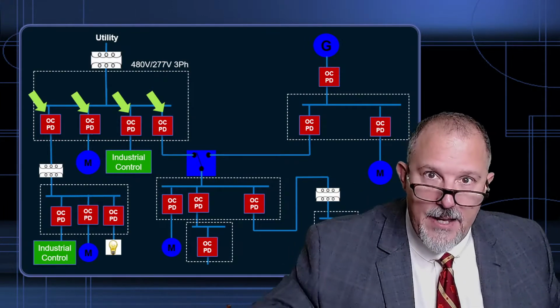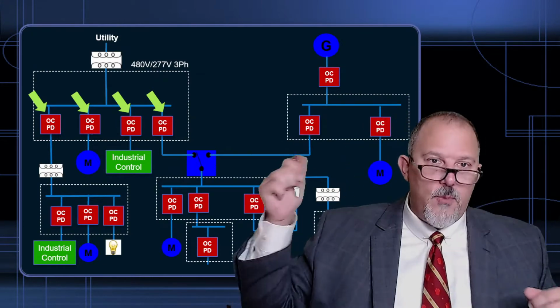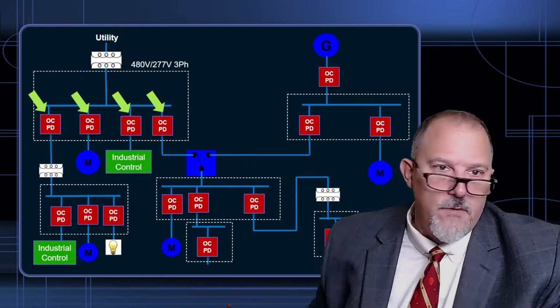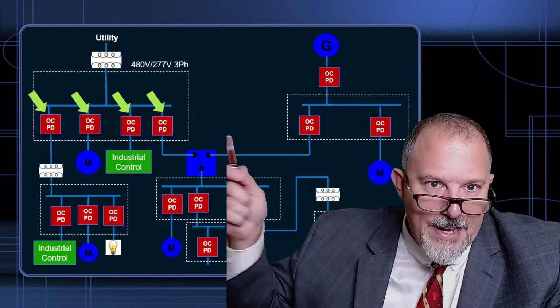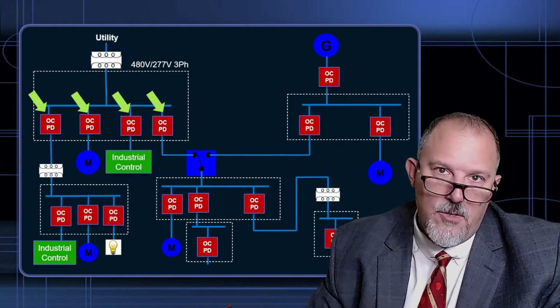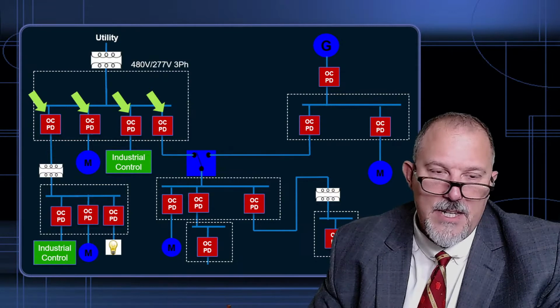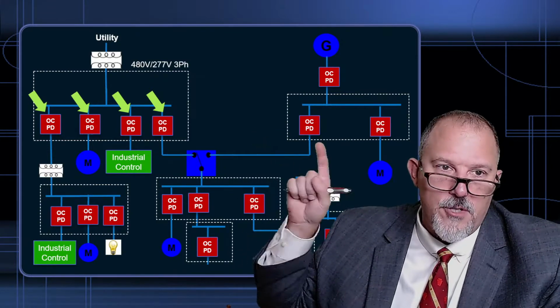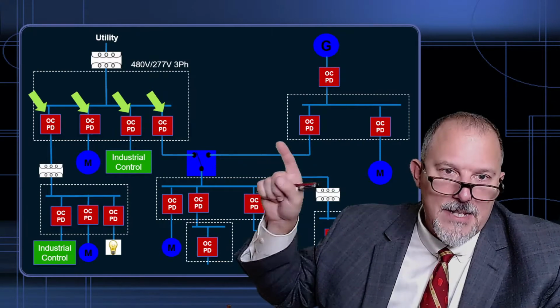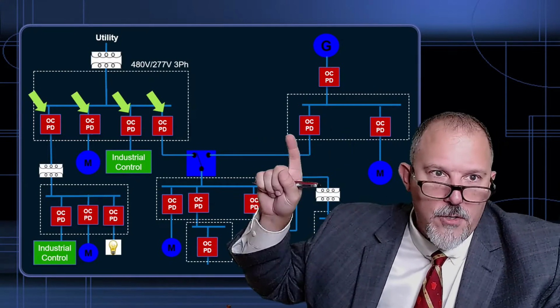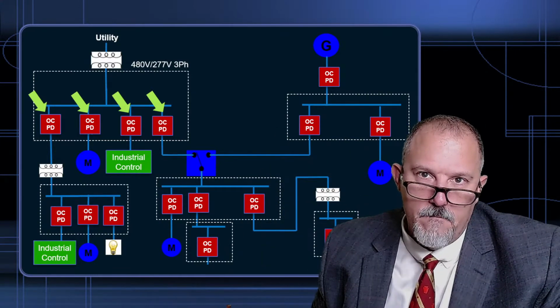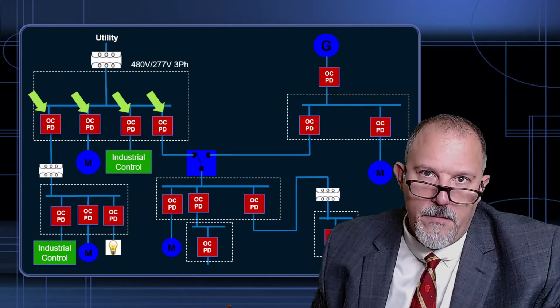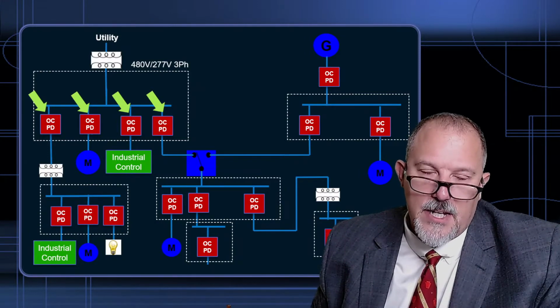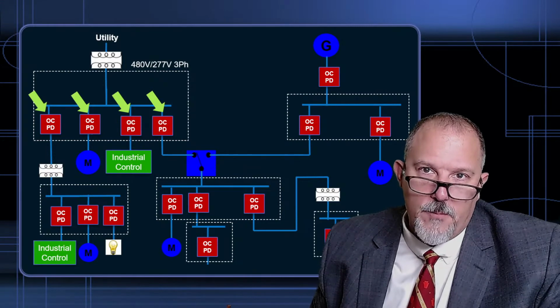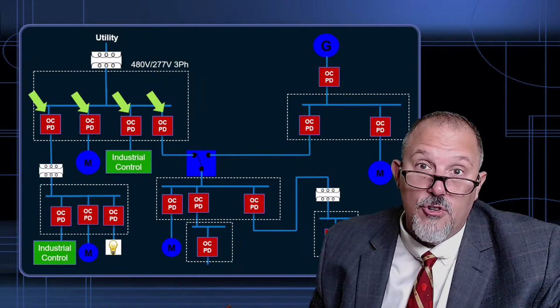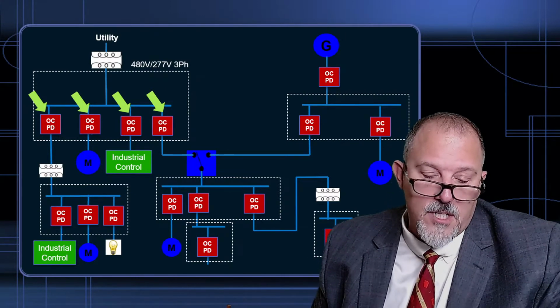Well, I could look at this table, and if I'm working on that equipment, the clearing time of each of those overcurrent protective devices, when I label that equipment, has nothing to do with how I'm going to dress. Why? Because the incident energy in that equipment is not based upon or determined by those overcurrent protective devices. The incident energy in that piece of equipment is determined by the overcurrent device on the primary side of that utility transformer, which is probably not going to open. If I have a 2-second delay clearing time on my overcurrent protection, that would put that into a double or triple digit incident energy, regardless of what you label this.